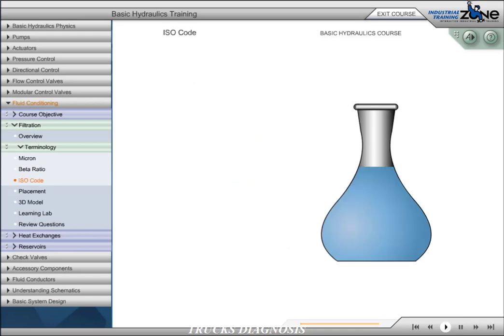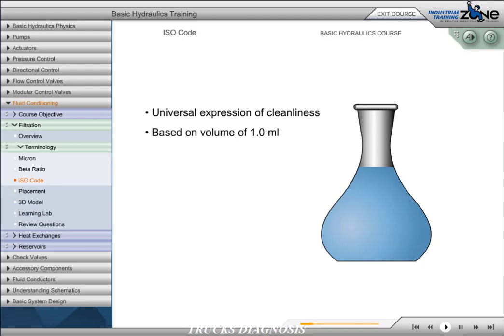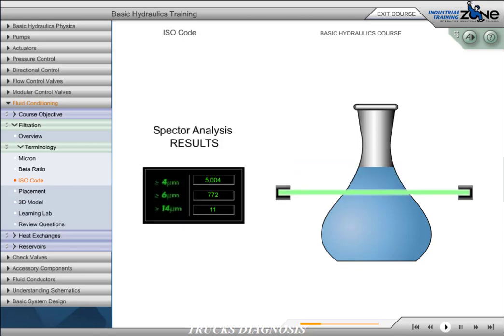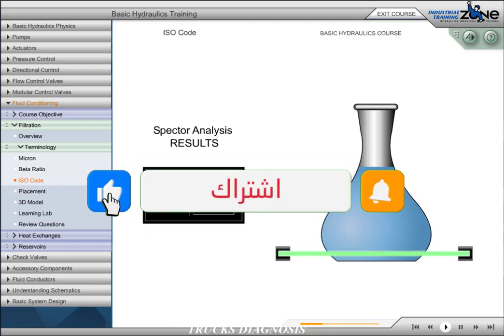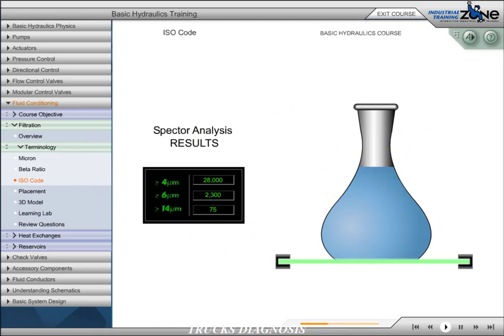To specify the cleanliness level of a given volume of fluid, we refer to what is known as an ISO code or ISO solid contamination code. This code, which applies to all types of fluid, provides a universal expression of relative cleanliness between suppliers and users of hydraulic fluid. Based on a milliliter of fluid, a particle count is analyzed using specific sizes: 4 micron, 6 micron, and 14 micron. These three sizes were selected because they give an accurate assessment of silt from 4 and 6 micron particles, while particles above 14 micron reflect the amount of wear-type particles in the fluid.